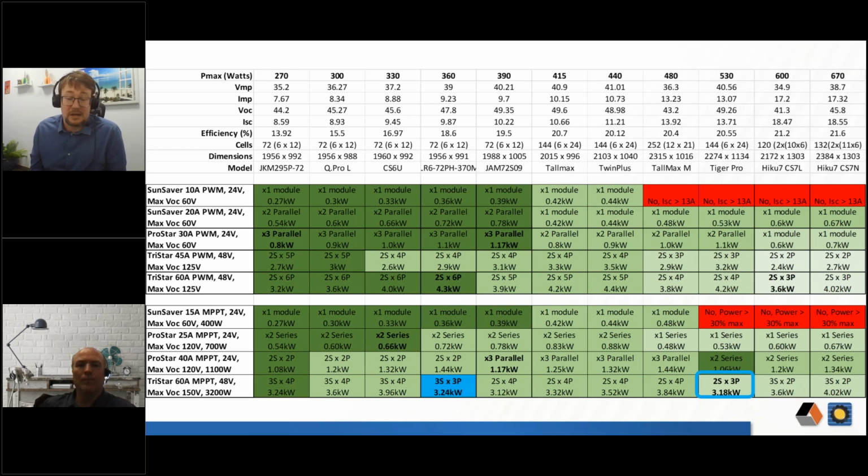It's also going to add a ton of weight to the module. It's also potentially going to be bigger than the monofacial version, but here is the most important thing that I want people to take away. All those things that I just said are going to impact your cost because you're going to have higher rated circuit protection. You're going to have a higher rated module to support the bifacial output, all that sort of stuff. But when you're sizing it from a reliability standpoint, all the people that I know are only applying about a 5% output to it.